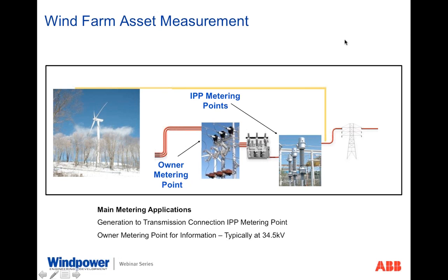When you look at a typical wind farm metering scheme, you really have two locations you have to consider. You've got the true IPP metering point. That's where the power passes from the generator to the transmission connection point. And that's typically a higher voltage application. You also have an owner's metering point back on the 34.5 kV side between the generator and the step-up transformer. And both of these locations have their own purposes and specifically identify efficiencies for both.